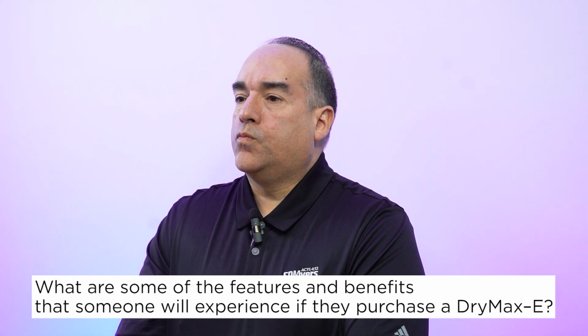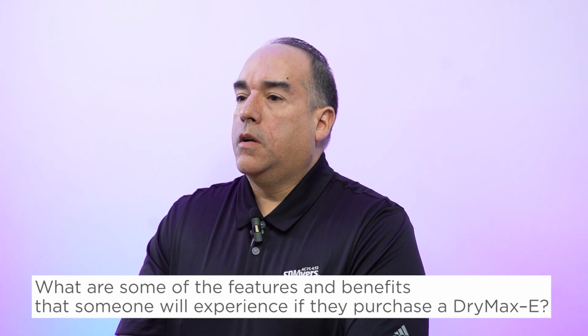What are some of the features and benefits that someone will experience if they purchase a DryMax E? Well, the main goal here is removing moisture from the oil and the paper insulation, which will increase the reliable life of your transformer. It can be installed and removed energized, which removes any required downtime and makes drying out multiple transformers easier. Easy to replace saturated media in the field or in the shop, lowering costs. The pump is sealless and magnetically coupled.